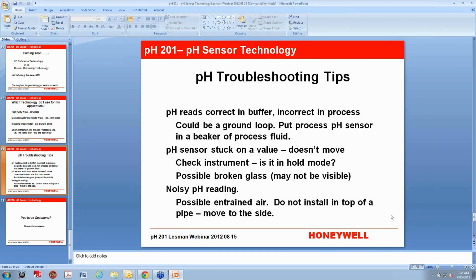The first one is I tried to list three things that I see happen a lot. And I see a lot of ground loops out there. You may have a mixer or something in your tank, and it may have a faulty ground that's been in there for a long time, and that can cause voltage to be in the process that doesn't belong. The pH sensor, because it's generating a millivolt signal, expects to go to instrument ground when the signal comes through. And if you have voltage in the process that doesn't belong, if your process is not at earth ground, that forces extra current to go through the sensor, and it gives you a wrong reading.